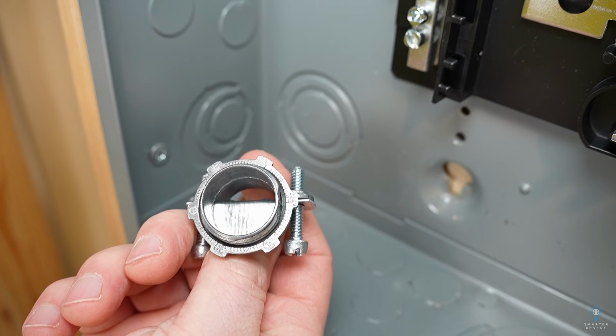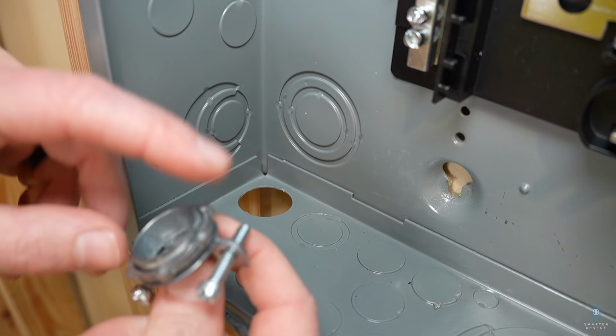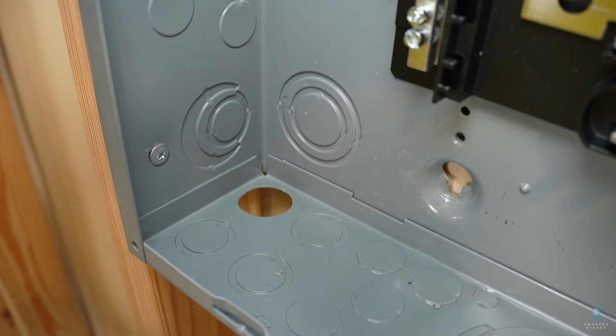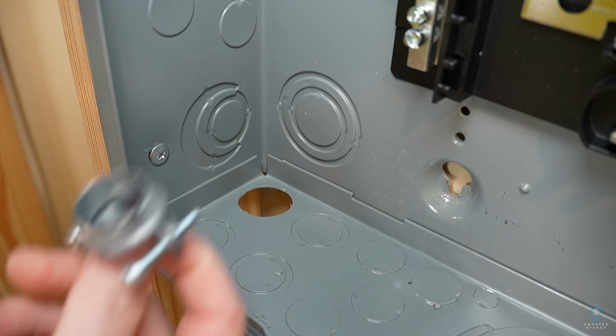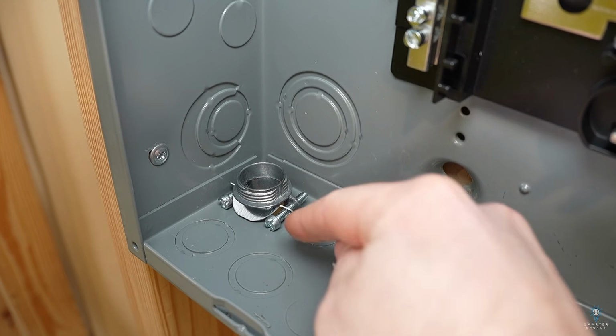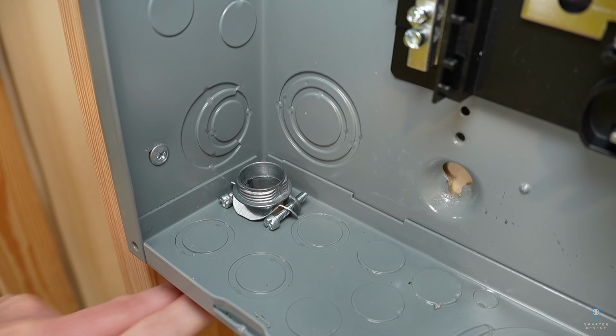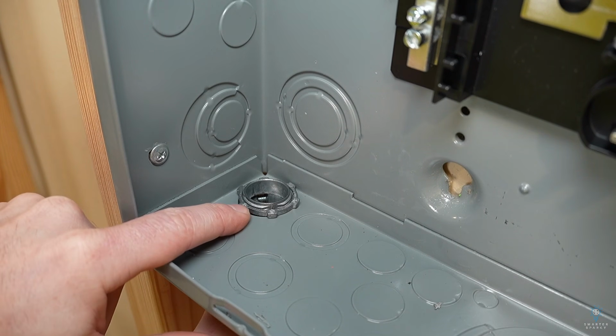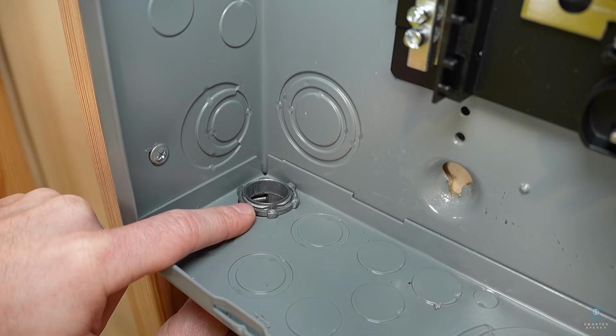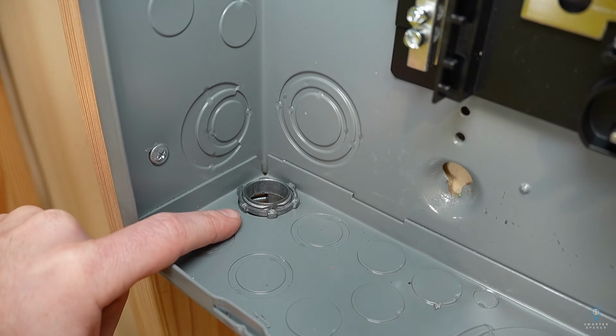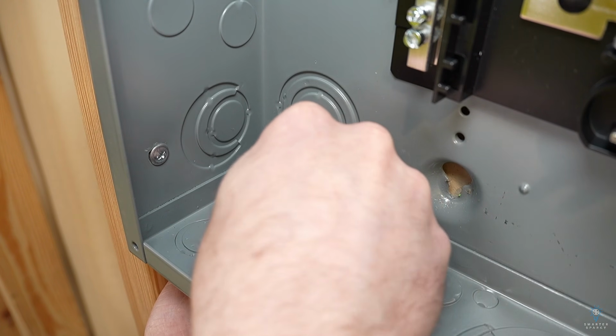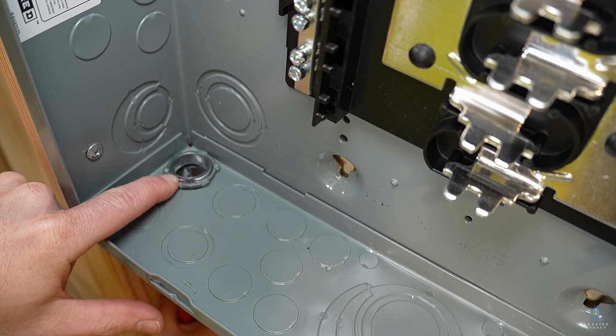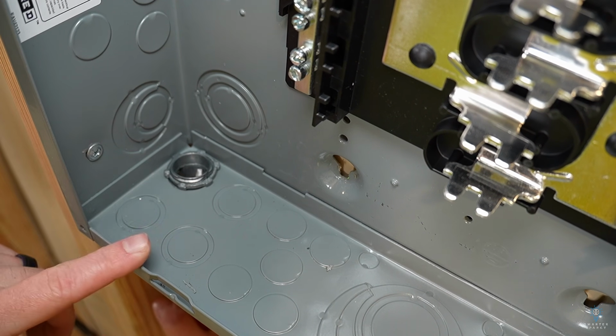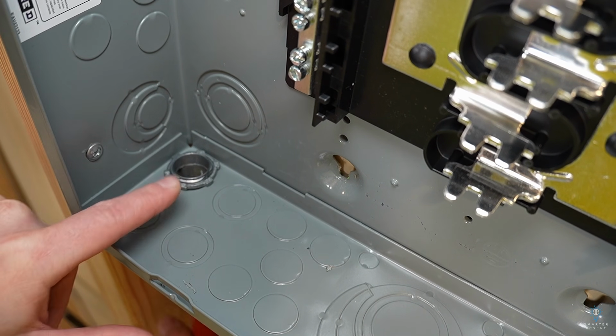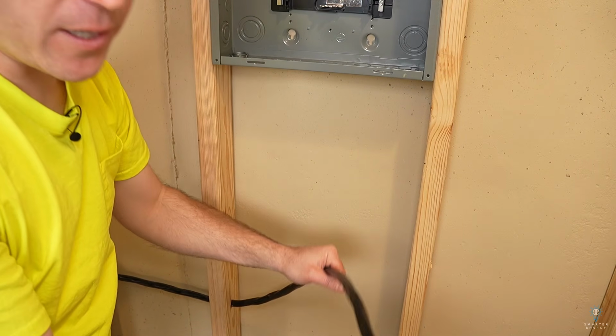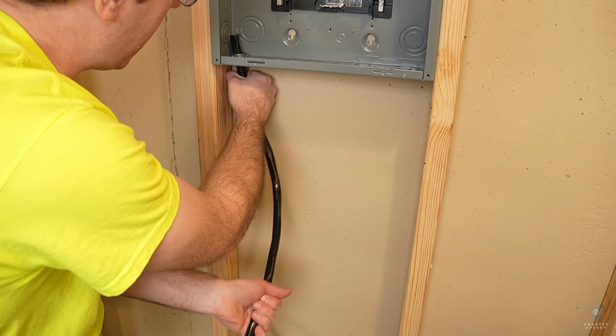And now we can take our cable connector and install it in the knockout that we just made. So we can take our lock nut off and poke it up from the inside. Again, I am orientating it this direction so the screws are facing out so we're able to tighten those screws down. And they make special wrenches to tighten these lock nuts down. I've never found the need for them. What I'll end up doing is rotating the bottom piece 90 degrees and then grab it with the needle nose at the bottom and twist it that last 90 degrees, and that tightens everything up. And now we can take our feeder wire and feed it up through that connector.